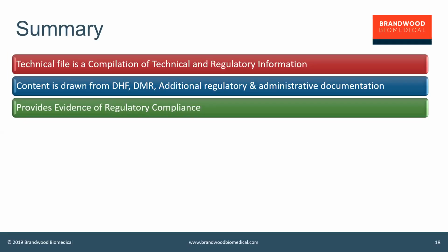Again, standards are out there because the use of consensus standards is getting more and more obvious from the regulators. So provide that evidence to show that you're compliant to specific standards, or that you comply to specific guidances or annexes or whatever it happens to be. Make sure that's within your technical file and it's spelled out explicitly. You do that a lot with your essential principles, your essential requirements, your GSPR, but having that evidence of all of this, the regulatory compliance, is key.